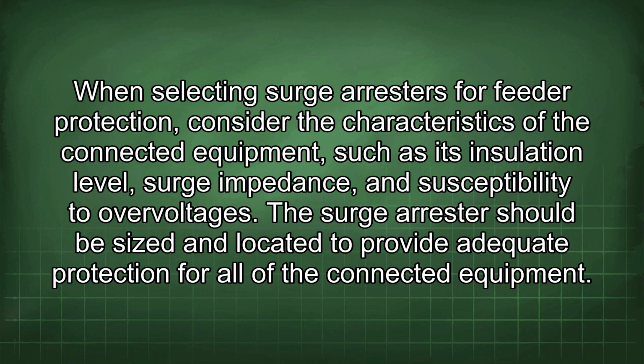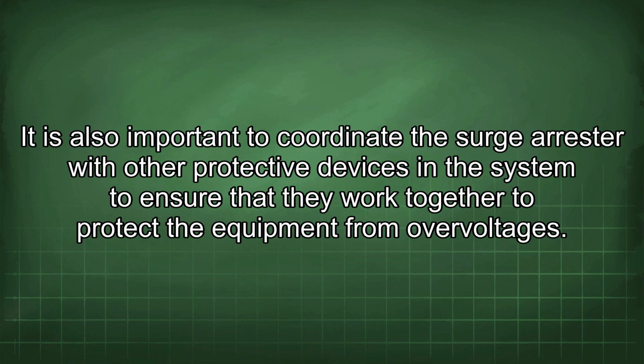When selecting surge arrestors for feeder protection, consider the characteristics of the connected equipment, such as its insulation level, surge impedance, and susceptibility to overvoltages. The surge arrestors should be sized and located to provide adequate protection for all of the connected equipment. It is also important to coordinate the surge arrestor with other protective devices in the system to ensure that they work together to protect the equipment from overvoltages.